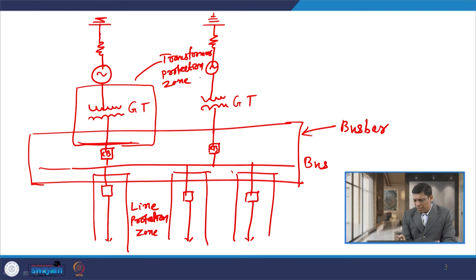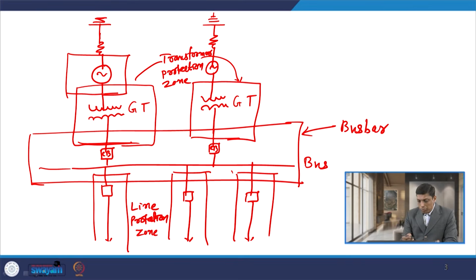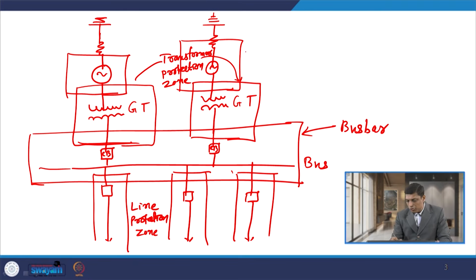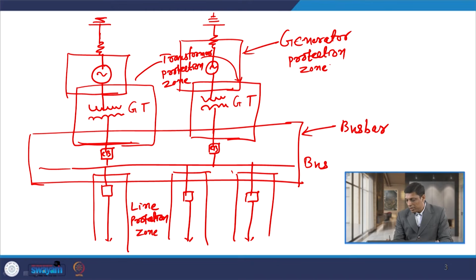Same way, if I define the protection zone for the generator, then the generator protection zone should be overlapped with the generator transformer protection zone. So, if I consider the generator zone, then the generator zone should be like this. So, both are overlapped. Similarly, here also we have the generator protection zone that has to be overlapped. So, this is the generator protection zone. So, all the protection zones should be overlapped.